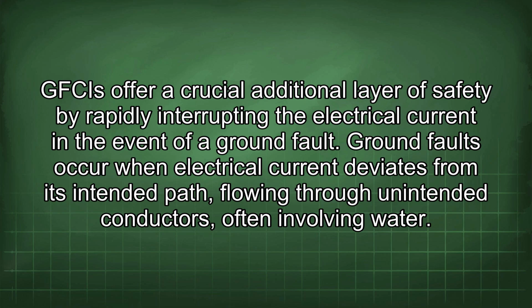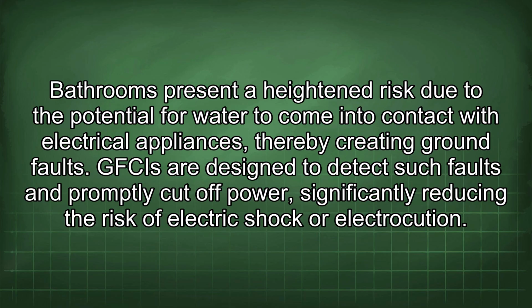GFCIs offer a crucial additional layer of safety by rapidly interrupting the electrical current in the event of a ground fault. Ground faults occur when electrical current deviates from its intended path, flowing through unintended conductors, often involving water. Bathrooms present a heightened risk due to the potential for water to come into contact with electrical appliances, thereby creating ground faults. GFCIs are designed to detect such faults and promptly cut off power, significantly reducing the risk of electric shock or electrocution.